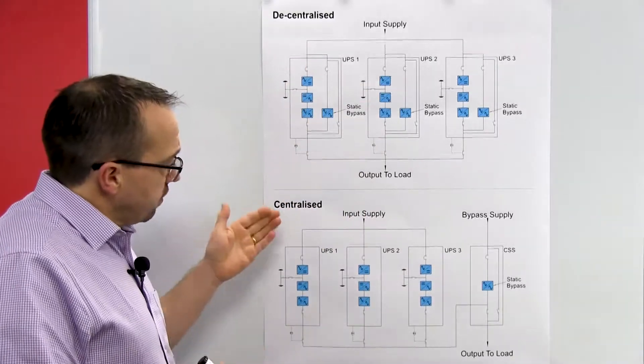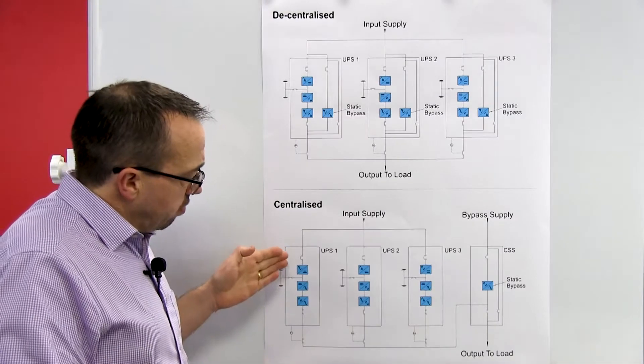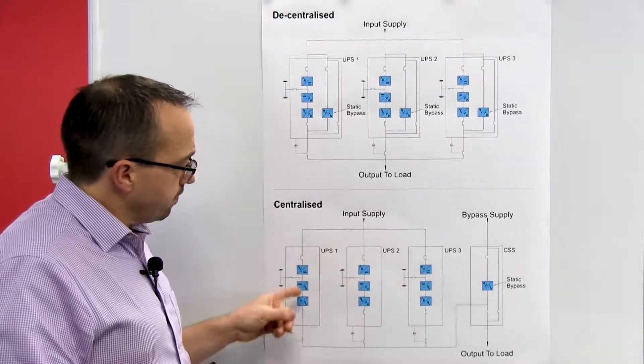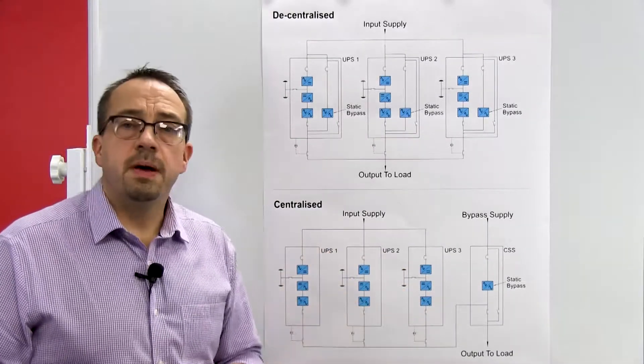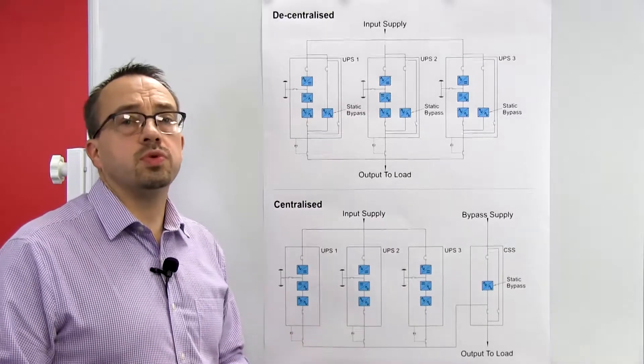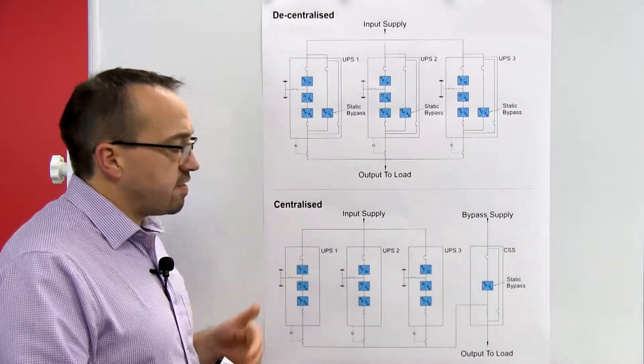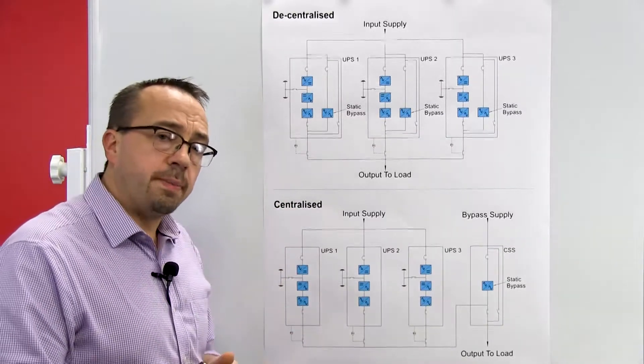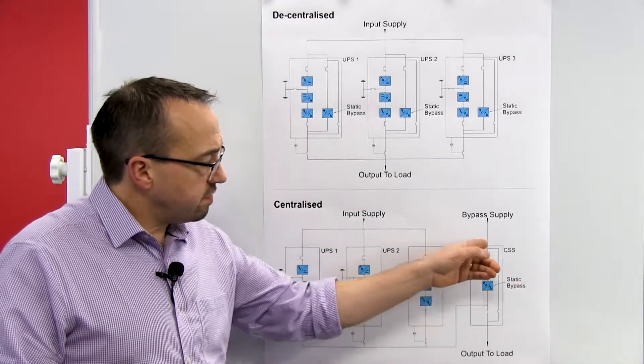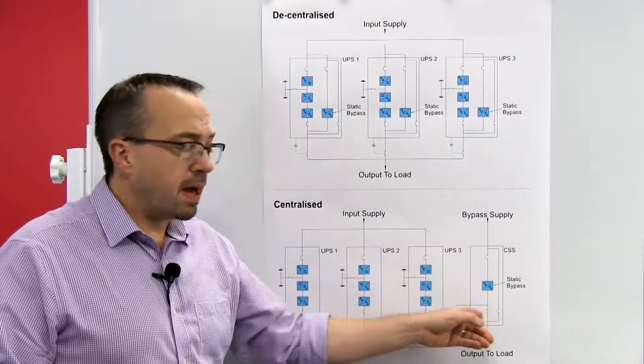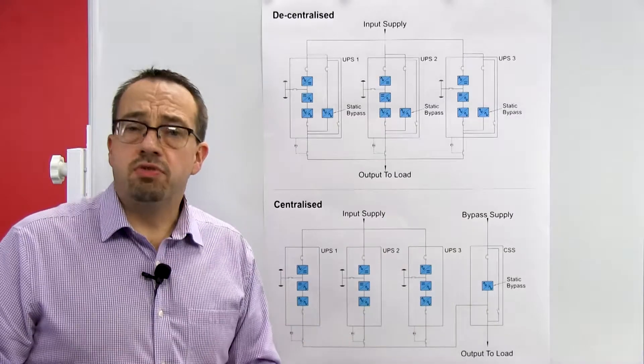In the centralized system we again have the same three UPS systems, albeit this time we don't have any static bypasses within the UPS modules. Because it is a centralized system, all of the static bypass components are located in a centralized bypass cabinet — hence the term centralized.